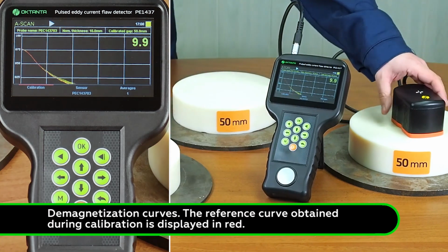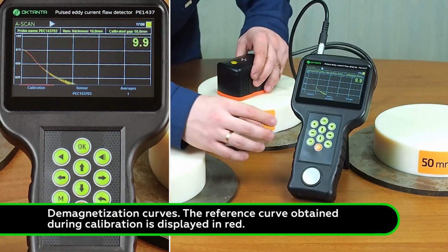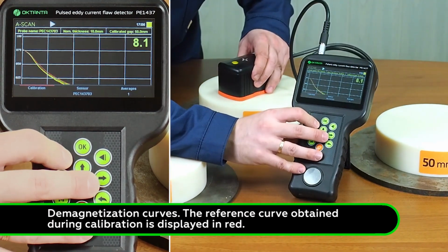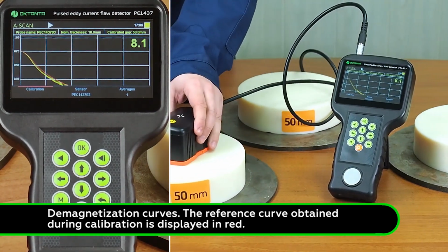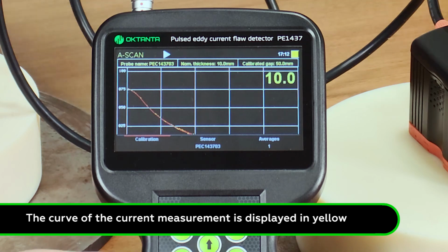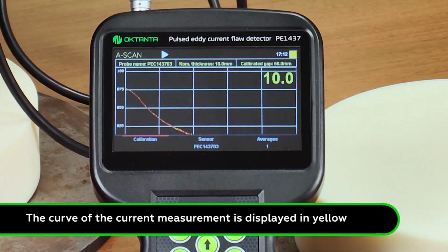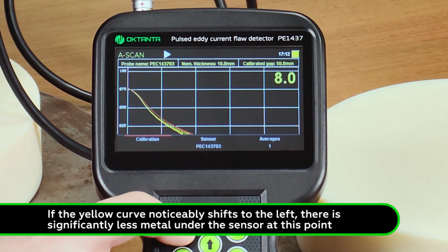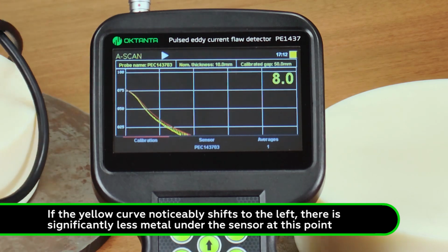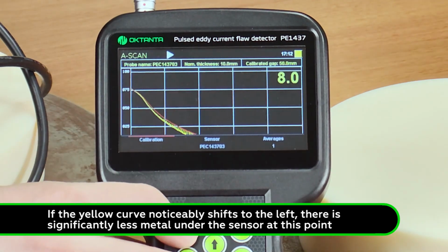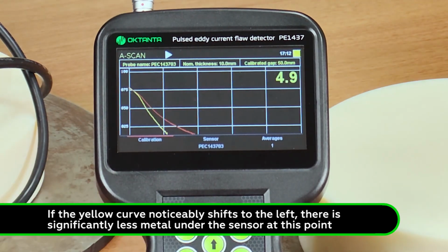The device displays a demagnetization graph, which is abbreviated as an A-scan. The reference curve obtained during calibration is displayed in red. The curve of the current measurement is displayed in yellow. If the yellow curve noticeably shifts to the left relative to the red one, it means that there is significantly less metal under the sensor, or a defect is detected.